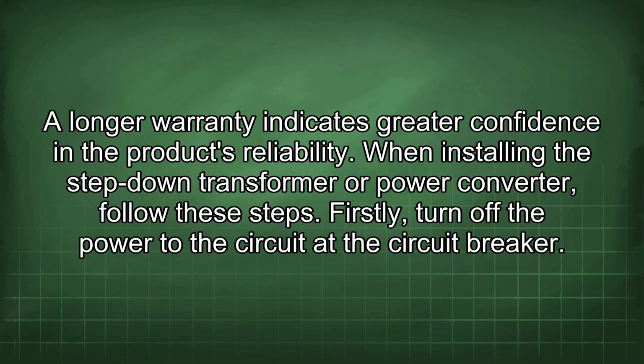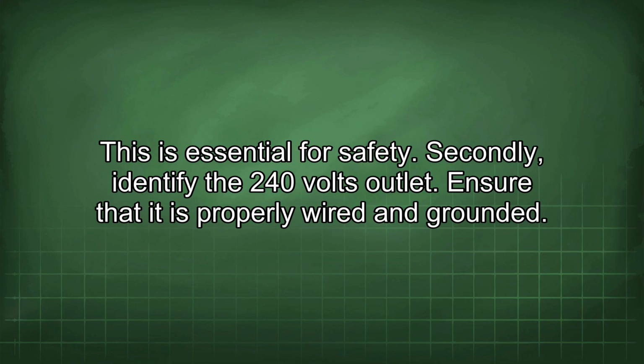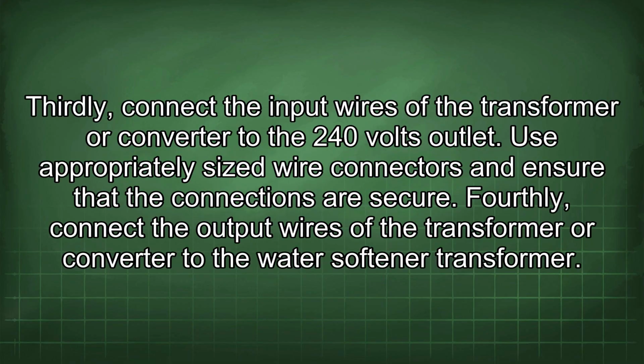When installing the step-down transformer or power converter, follow these steps. Firstly, turn off the power to the circuit at the circuit breaker. This is essential for safety. Secondly, identify the 240 volts outlet. Ensure that it is properly wired and grounded. Thirdly, connect the input wires of the transformer or converter to the 240 volts outlet. Use appropriately sized wire connectors and ensure that the connections are secure.